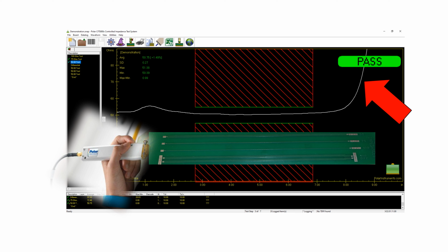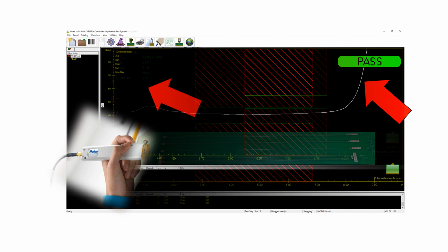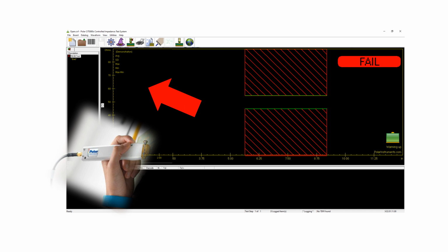It's also useful to know if your probe's connected. So one thing you can do is hold the probe in open air and run a test. And you should see the end of the probe rise to an open circuit when there's no coupon present. It's a really useful test, and if you see nothing there, either your probe is set up incorrectly or not connected up tightly to the CITS, or you might find that you've set up the test limits wrongly.